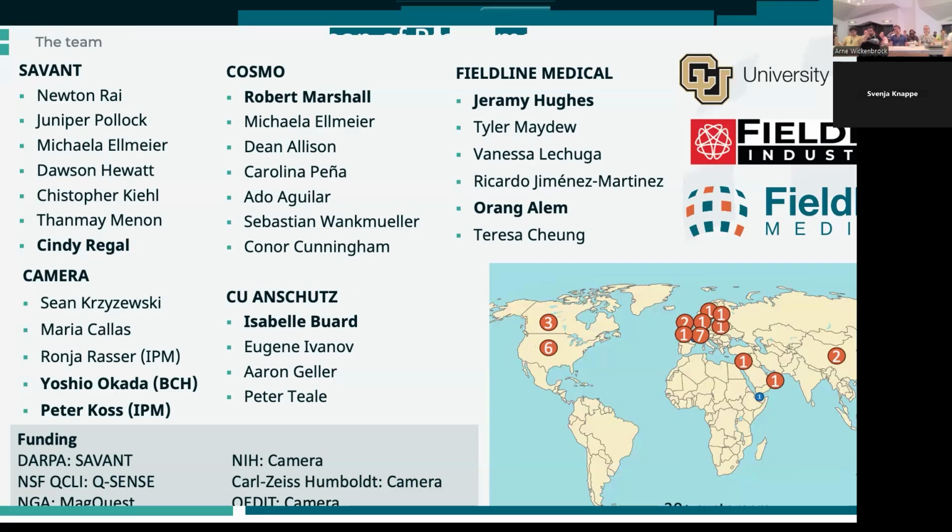One advantage that I do get from making the system smaller rather than gigantic is I don't necessarily need a room. Depending on my application, I can build something that looks like an MRI, push my person in, and take them back out. For some applications that works. For some it just doesn't, because the person wouldn't be still, or movement is important to my study. So that's a differentiator, but it is an option, and it does reduce the cost drastically, with smaller shields.